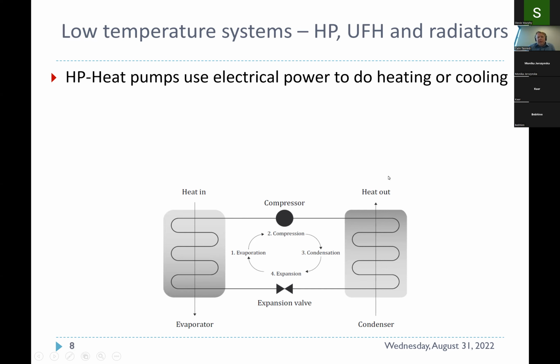Typically, this is where we have a plate heat exchanger, and on one side we have the refrigerant gas, and on the other side we have the water side. In this instance, the gas will condense and go into liquid form, go through an expansion valve, and the circuit goes over and over again, thousands of times.